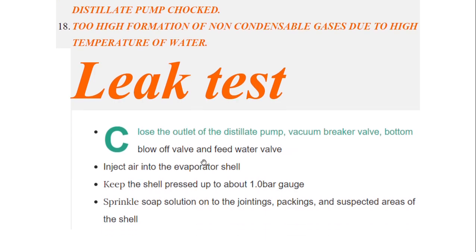Now we have the leak test — that was the major topic I wanted to cover. The leak test is simple. We close the outlet of the distillate pump, the vacuum breaker valve, the bottom blow-off valve, and the feed water valve. We close all these valves because we are taking the leak test and we don't want air to pass through anywhere.